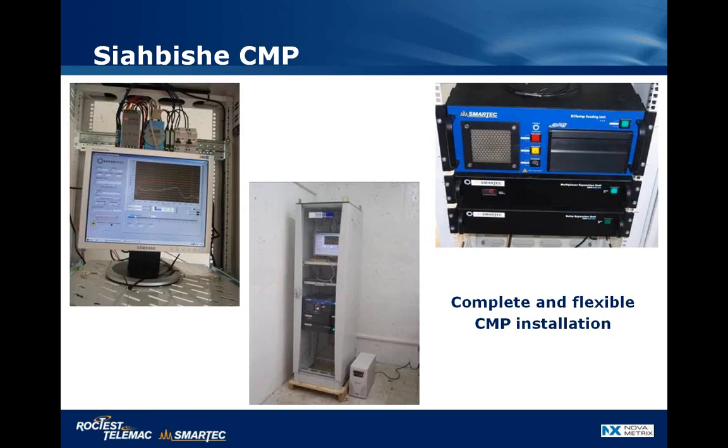A dedicated control room where the instrumentation rack was located was specifically built on the crest of each dam. The rack contains a display, the DiTemp unit with its accessories, the server PC where the DiveView software is installed, and the heating module necessary to heat up the cable at scheduled times. All the system was plugged into a network stabilizer and UPS in order to prevent loss of functionality in case of power breakdown.